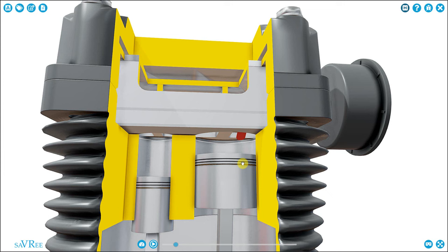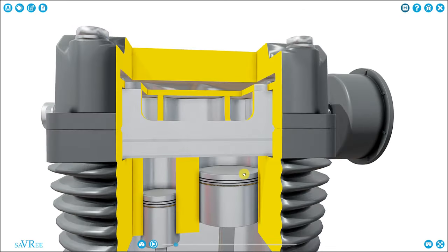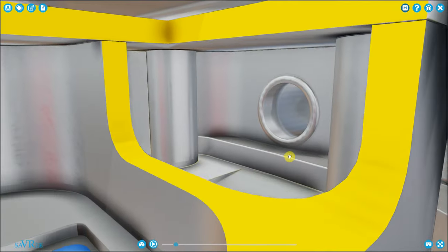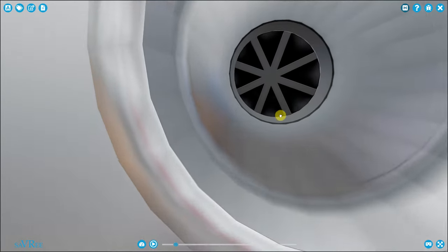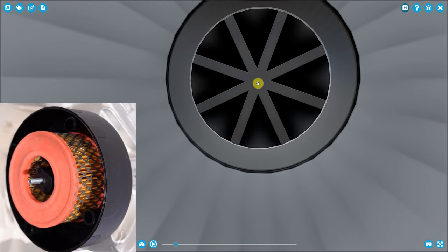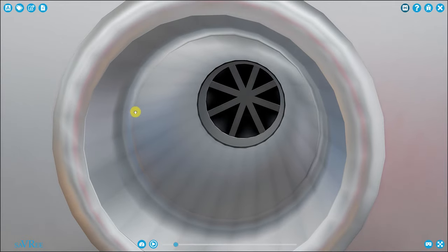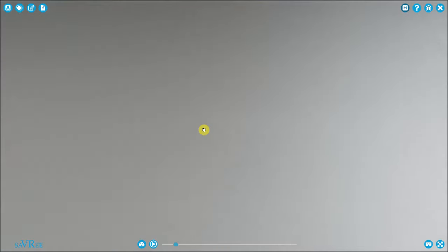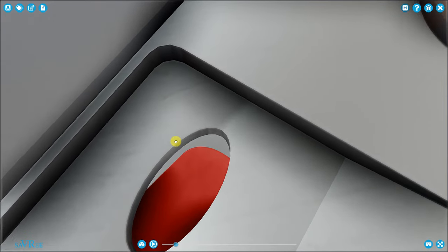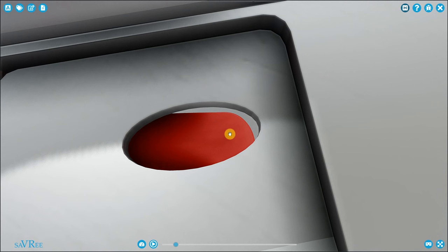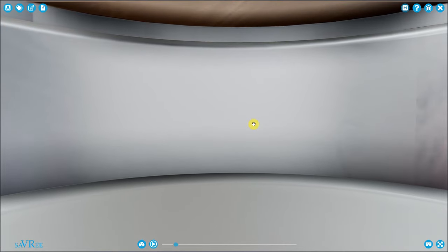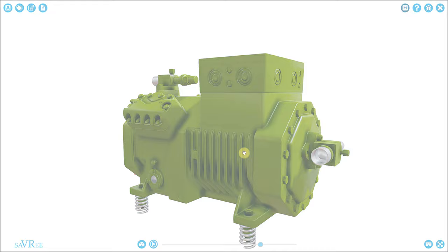Once we've drawn air into the air compressor, you can actually see where the air comes in — it comes in through this hole. There's our air compressor filter; the filter would be located where this star shape is here. The air comes in and is then drawn into our cylinder. It's going to be drawn into the cylinder through this red valve, this red flap. These valves are usually slightly more complicated, but let's stick with the basic design for now. So air is drawn in, passes through this space, goes into the cylinder, and once inside the cylinder, we're essentially trapped between the cylinder liner and the piston.